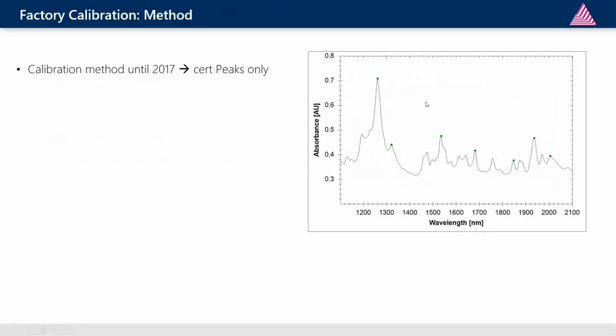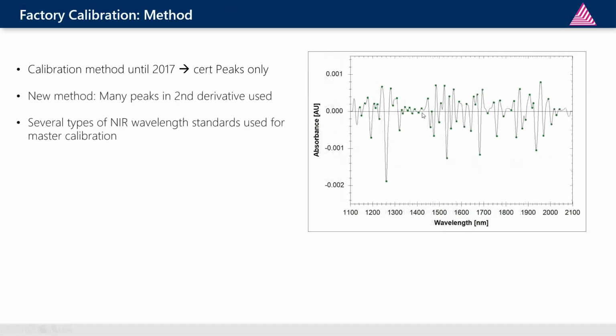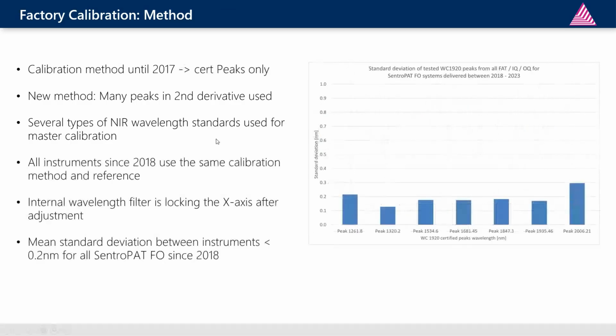So what did we do? We had been calibrating or adjusting our instruments until 2017 based on the certified peak locations, for example, of a 1920 wavelength standard. This is just the green mark points here. We then changed that method to use peaks from a second derivative spectrum from the same standards. From 6 peaks, we got to close to 65 to 70 peaks usable for the x-axis adjustment, with a very nice spread over the complete range. We were also using several NIR wavelength standards for the master calibration we built at this time. Since then, we are calibrating our instruments with that method.